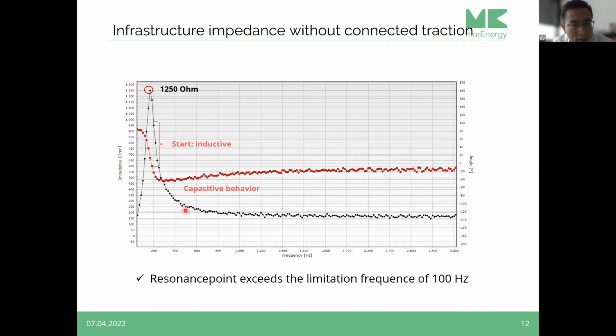The black line is the absolute value of the impedance, and the red line is the phase. We have a resonance at 180 hertz with 1.2 kilo ohms. Typical of this curve is that we start with inductive and then get capacitive behavior, and this resonance comes together because on this testing infrastructure there is a transformer and also a filter system installed, and that's the reason why we have this characteristic parallel resonance. What we can see here is that the resonance point exceeds the limitation frequency of 100 hertz, so we are within the norm.